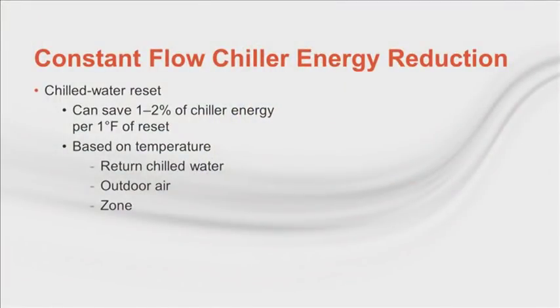Now let's move on to operation. Constant chilled water flow systems have fewer optimization opportunities than other configurations. Now that's not necessarily a bad thing. It helps to keep things simple. If you follow the advice of many and designed a high DeltaT system, you're well on your way to a high-performing chilled water system with very low pumping energy. But if you've used colder water to get your higher DeltaT, you may be concerned about the energy used by the chiller to make it that cold at part load conditions. One strategy commonly applied in constant flow systems is chilled water reset.